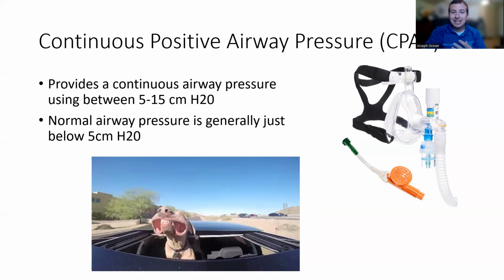And understanding that a standard airway pressure is generally around 5. So in Orange County, we set ours at a minimum of 10 because the understanding is that if you start at 5, you're probably not accomplishing much if that's the standard airway pressure, right? And so once again, you're providing a continuous airway pressure. So it doesn't alternate based on inspiration or expiration, but every time they take a breath in, you have the air that they're taking in, so the force that they generate, in addition to the continuous positive airway pressure provided by this device. And then when they exhale, and that additional force from the inspiration goes away, there's still that continuous positive airway pressure.